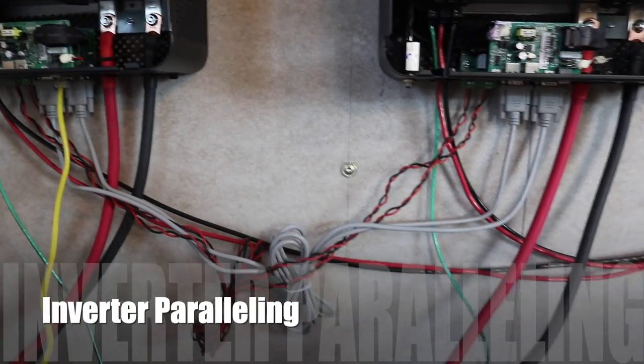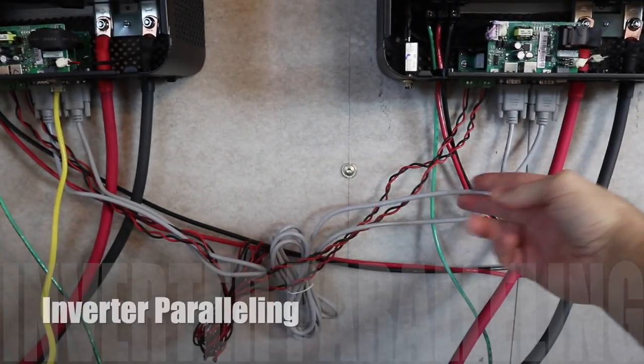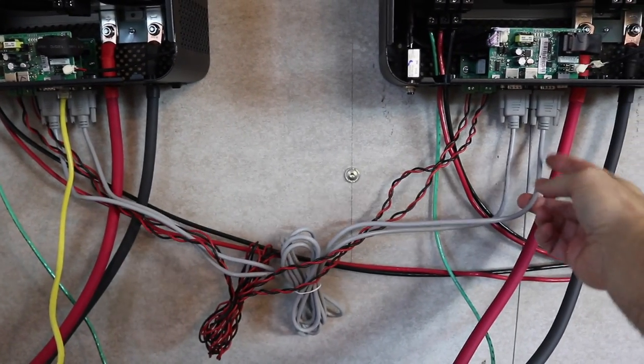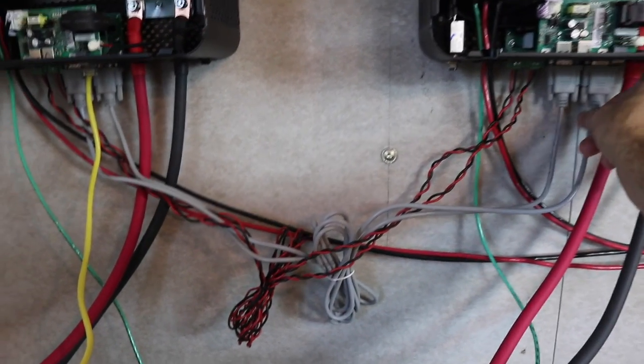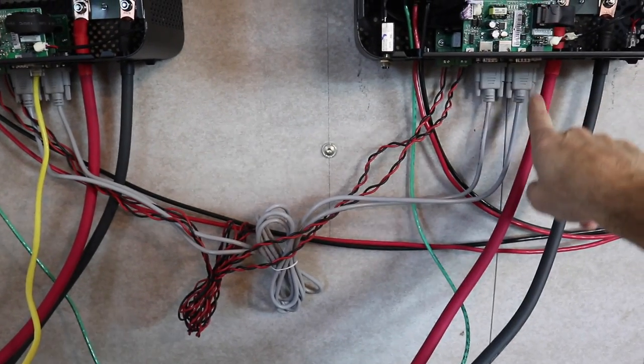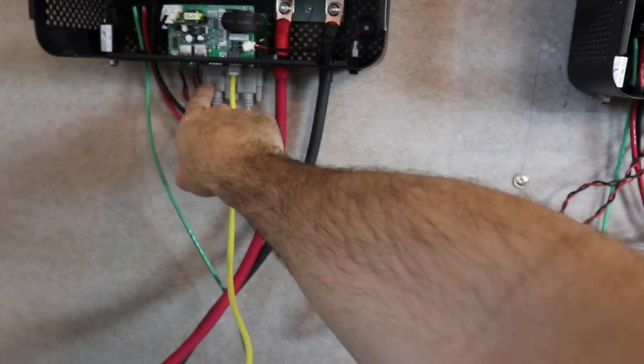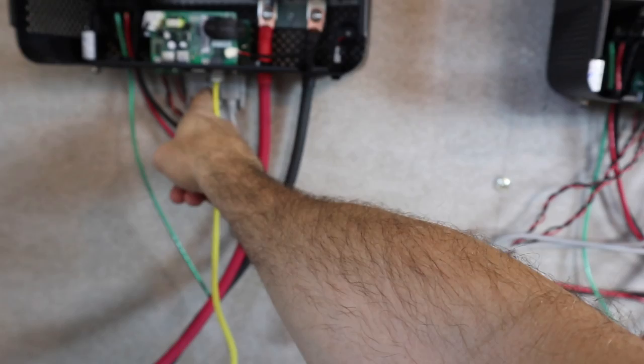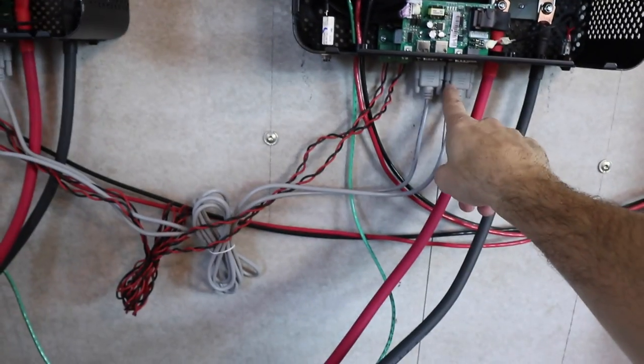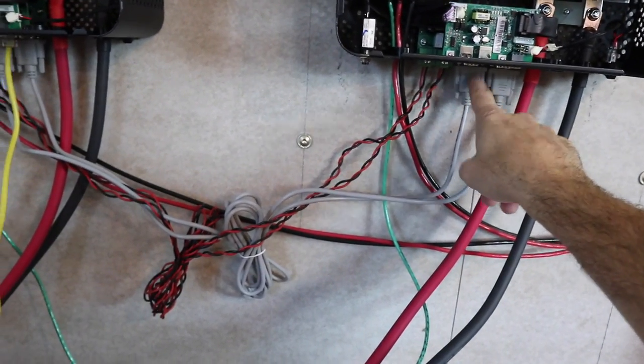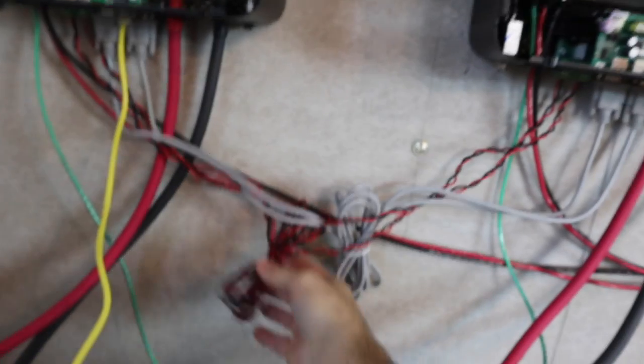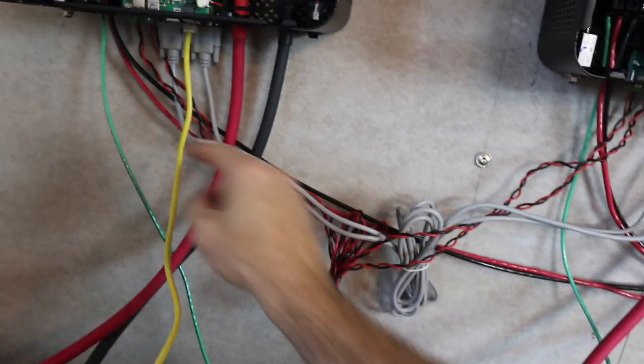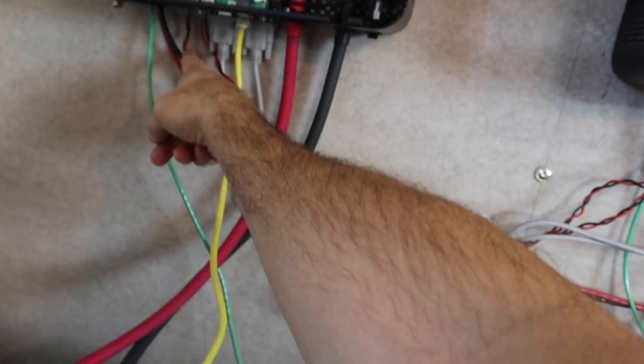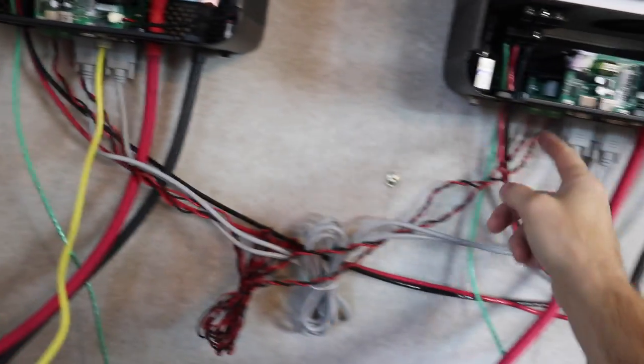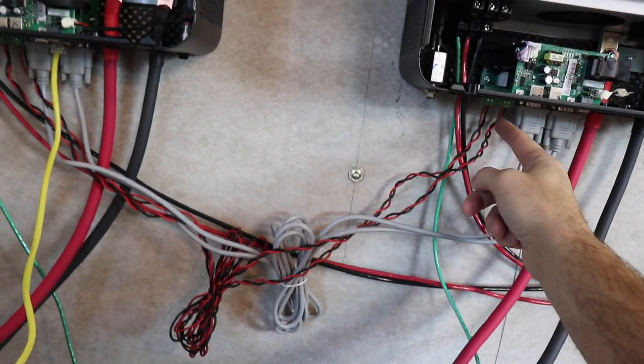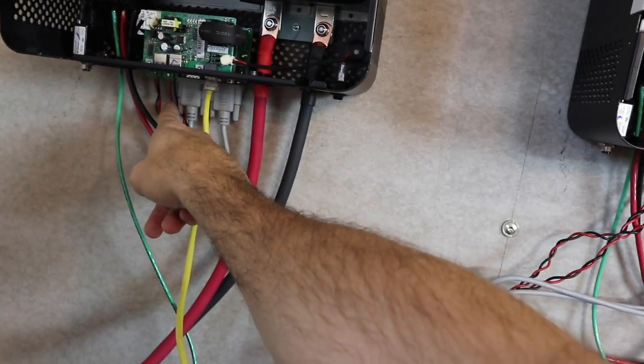So this is covered clearly in the manual. These communication cables here, the old school style is pretty funny, that goes outside to outside. So on this inverter, it's the one on the left. This one, it's the one on the right. And then inside to inside for the other cable. On these additional communication wires, they go same to same. So left on this side to left on this side, and then right on this side to right on this side.